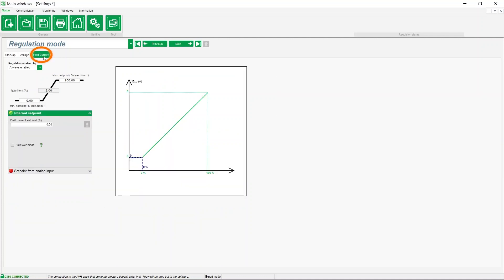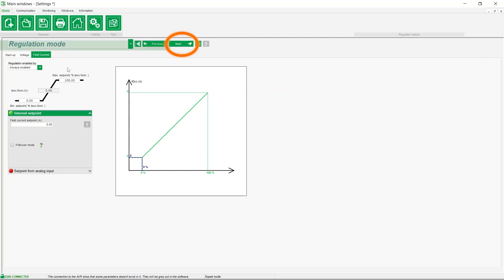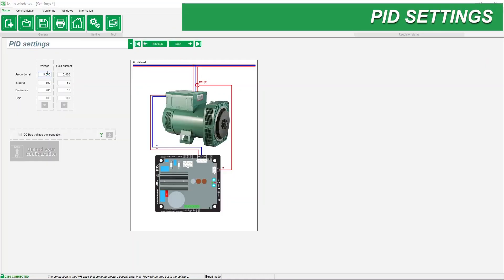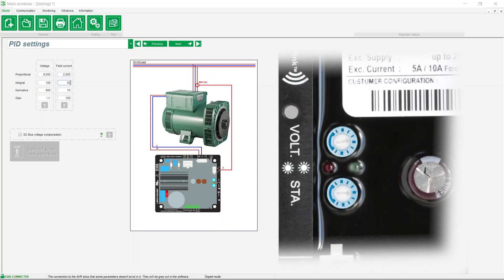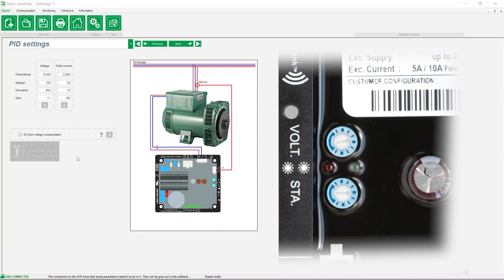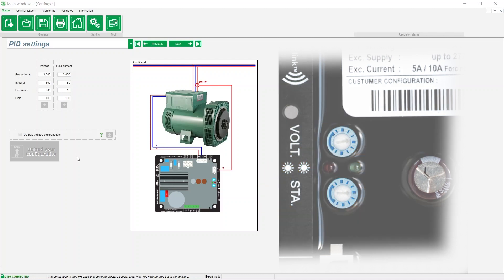You have the possibility to manage excitation current, but this regulation mode is generally used by experienced technicians for specific applications. Now let's see the PID settings. These are automatically filled based on the machine and can be adjusted during commissioning if necessary. When the internal potentiometers are enabled, the gain is adjusted via the potentiometer STA, and in this case the gain value will be grayed out.